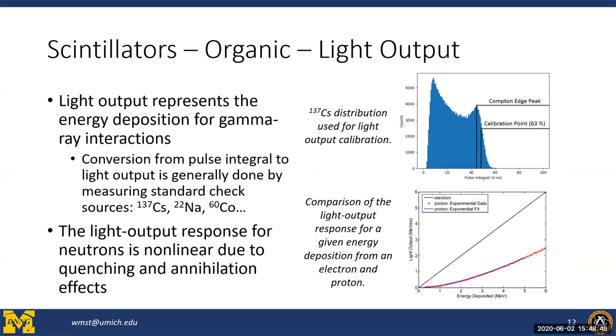However, this is material, geometry, and detector dependent. So we can definitely have cases where this light output curve will change and actually needs to be calibrated for any given type of detector.